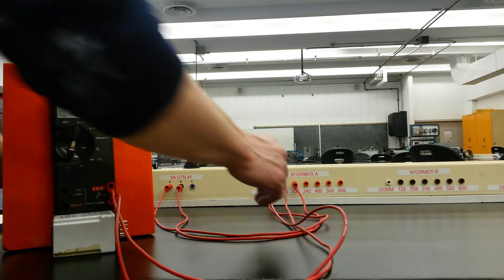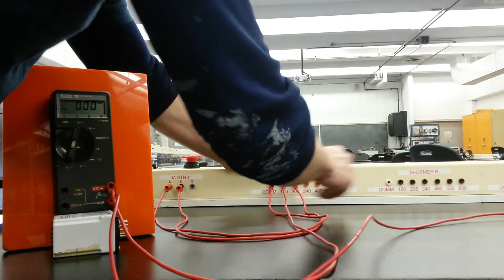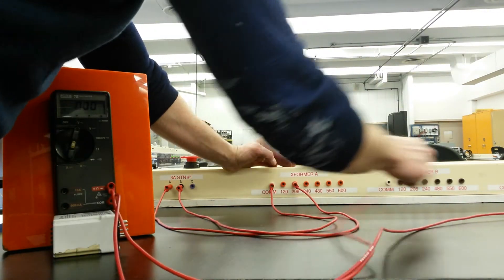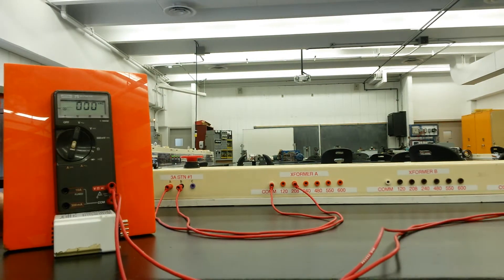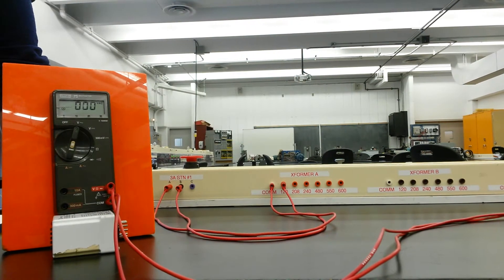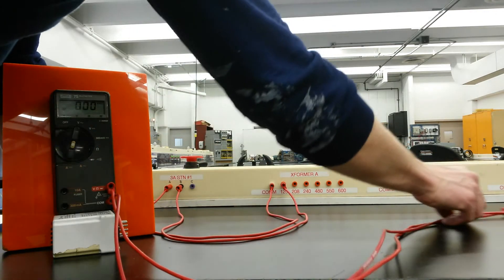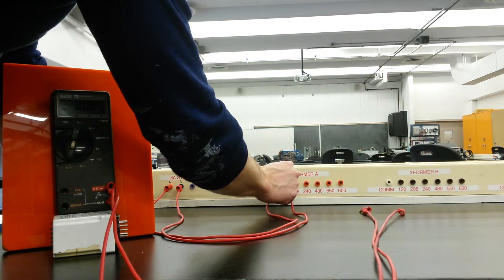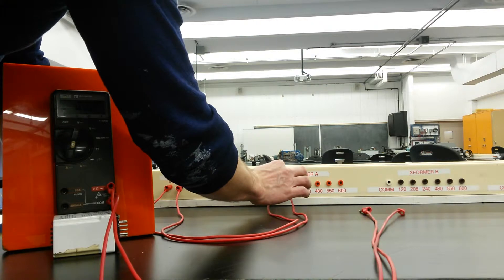Now, some of you guys will want to be donkeys. As much as I tell you not to do this, you will try to take the 208 volt feed and you will feed the 120. That voltage, the 208 going to the 120, is now across fewer turns.